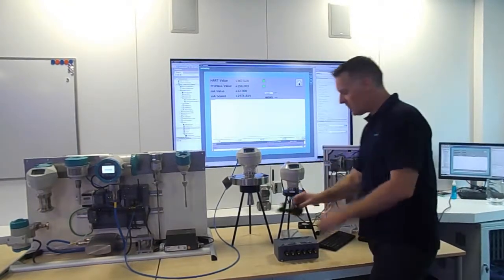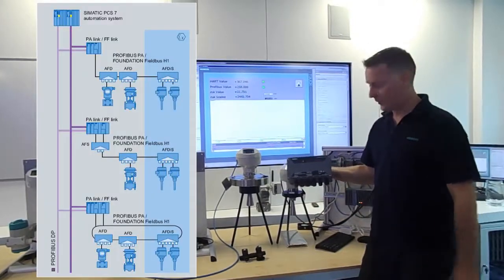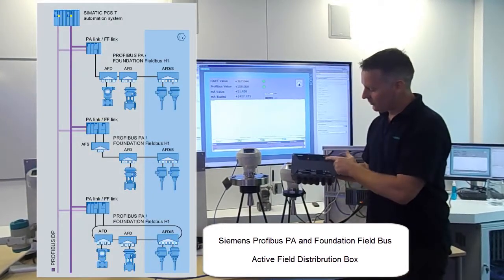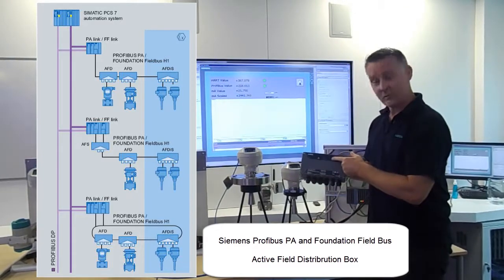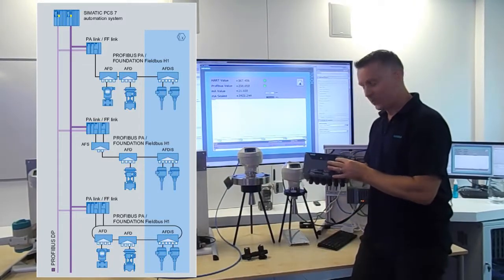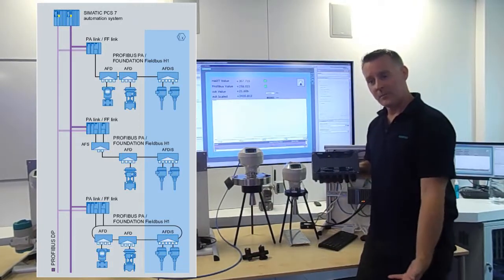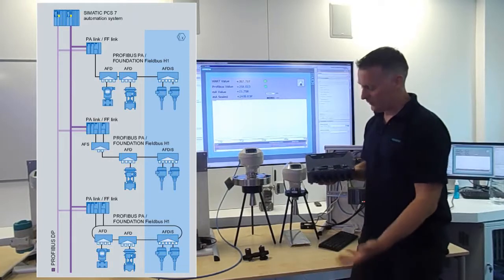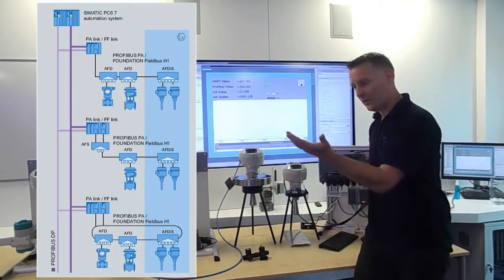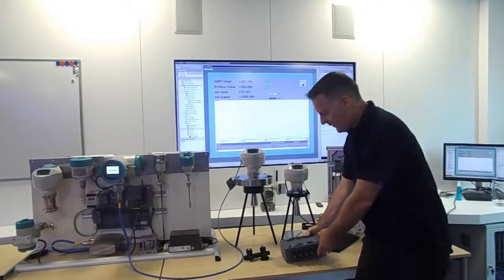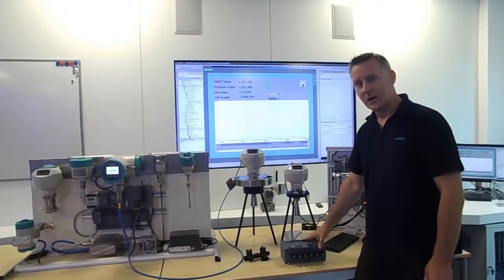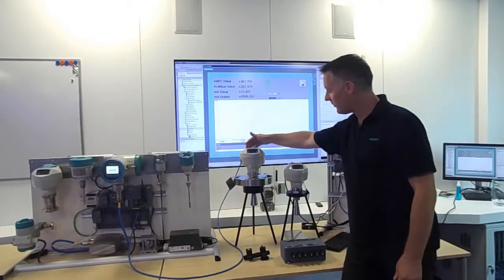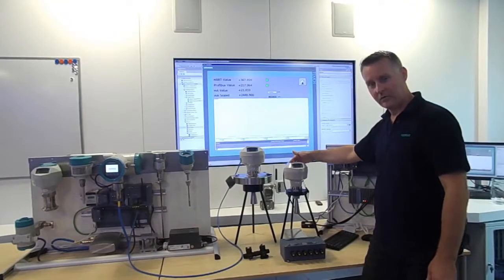So then you would move over to something called an AFD or similar products are available. So this again separates the trunk from the spurs. So if we did get water ingress on one of these spurs we would only lose that. But because it's got short circuit protection built into this it would prevent the Profibus value getting to the PLC. But you would only lose that one value and the rest of the network would carry on working. So as you can see there's various solutions but really the best solution is good mechanical installation, using the right cable glands, using a digital technology that's not affected by noise and gives you more accuracy.